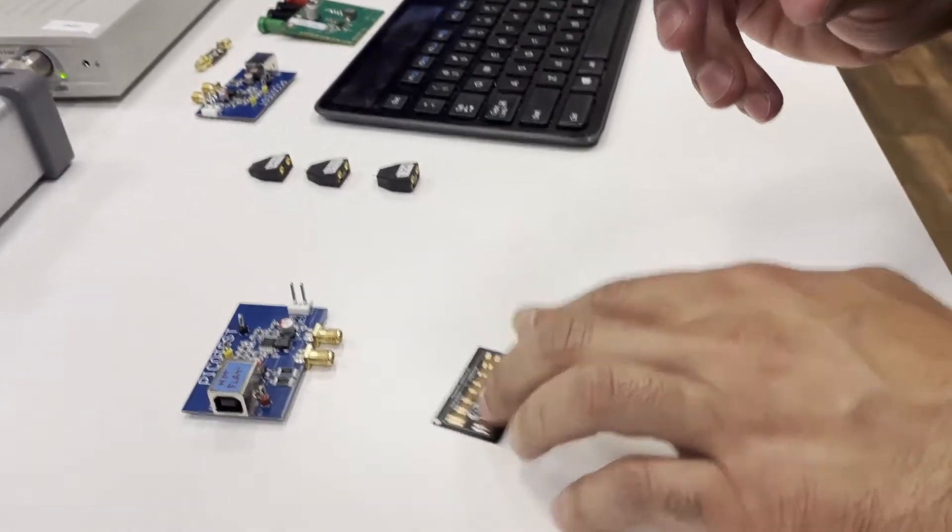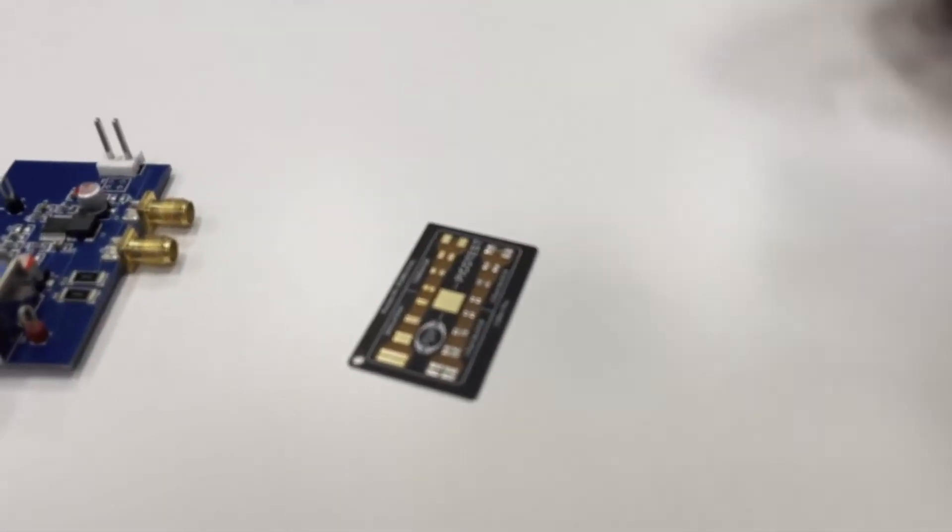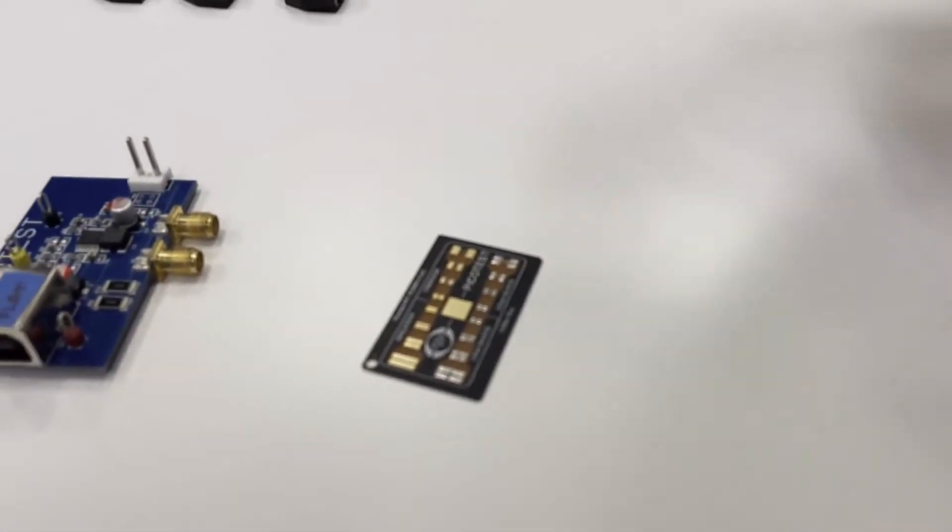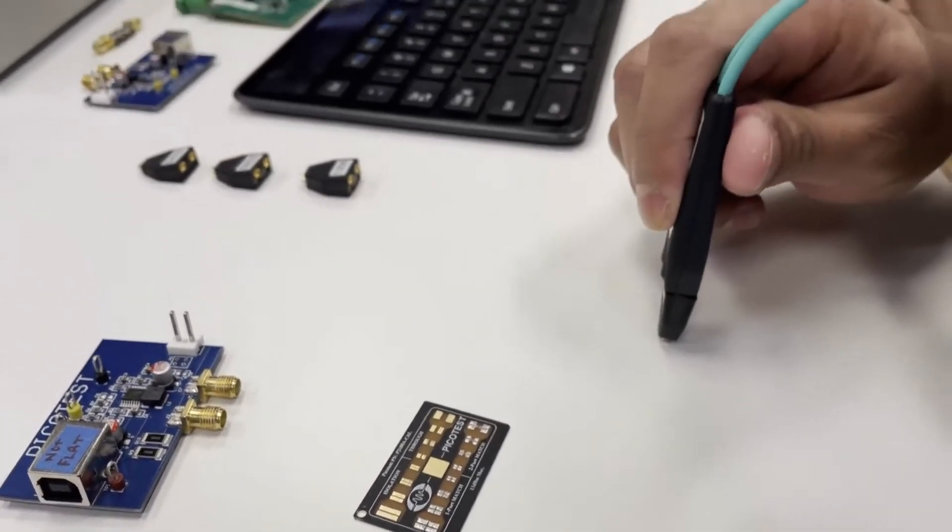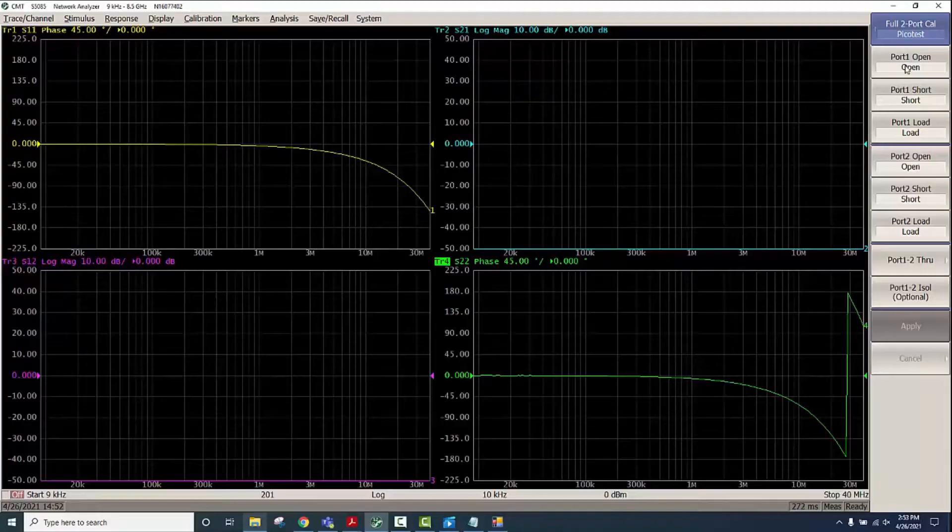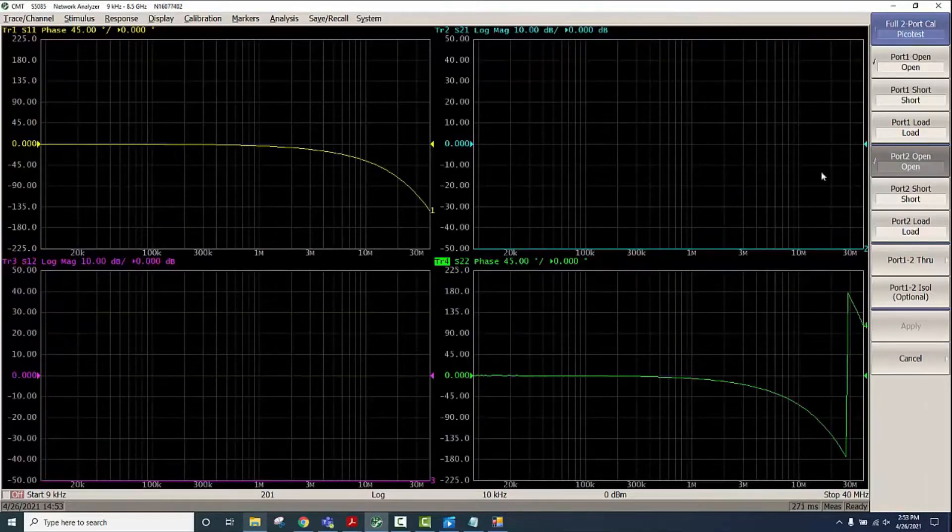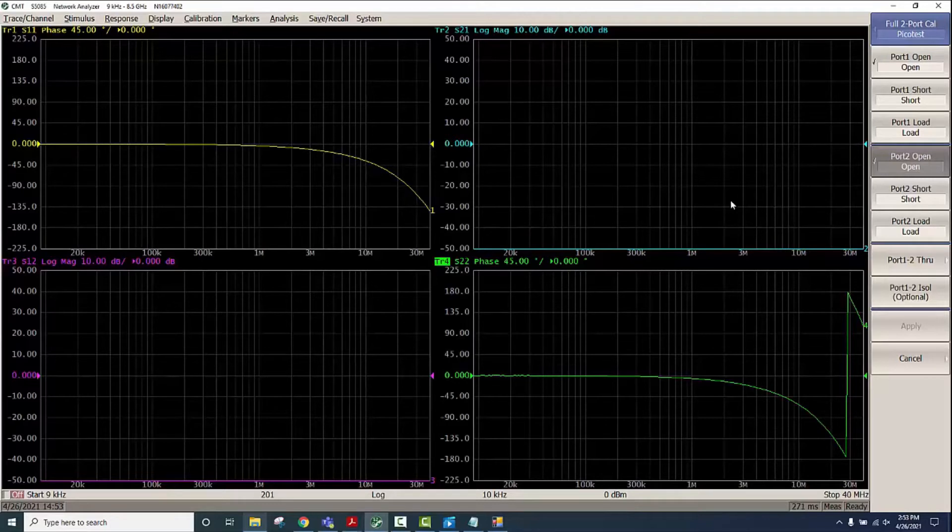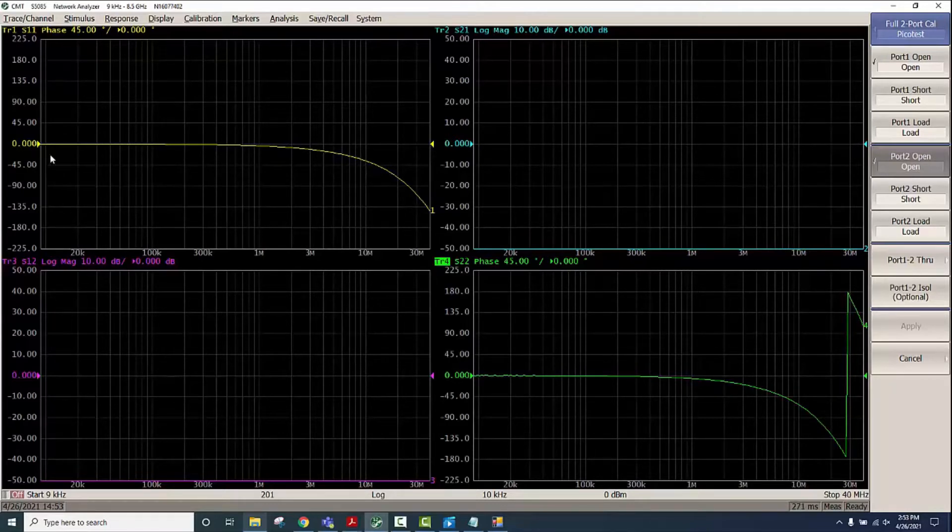Now here is the substrate. First what we'll do is an Open, so we're not connecting to the cal substrate at this time. We're just doing the open connection. You can see S21, S11, and S22 phase is close to zero there at low frequencies. Next what we'll do is the isolation.